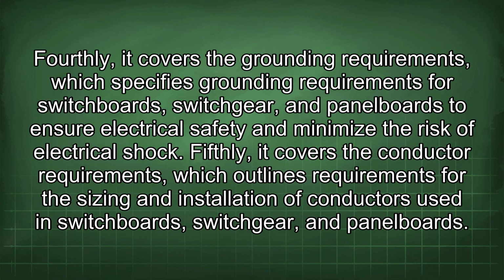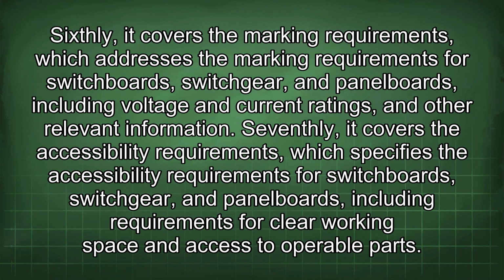Fourthly, it covers the grounding requirements, which specifies grounding requirements for switchboards, switchgear, and panel boards to ensure electrical safety and minimize the risk of electrical shock. Fifthly, it covers the conductor requirements, which outlines requirements for the sizing and installation of conductors used in switchboards, switchgear, and panel boards. Sixthly, it covers the marking requirements, which addresses the marking requirements for switchboards, switchgear, and panel boards, including voltage and current ratings and other relevant information.